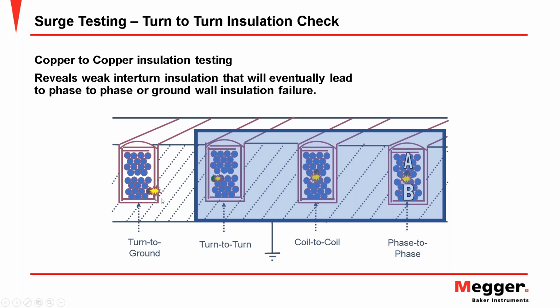So over here on this graphic, we see the ground wall insulation represented here in the slot between the conductor and the frame. The turn-to-turn or copper-to-copper insulation is between individual turns in the coil. It could possibly be between two adjacent coils, so copper-to-copper between coils. And if those coils happen to be in different phases, so if the top coil was, say, phase A, the bottom coil was phase B, that phase-to-phase barrier is also considered a copper-to-copper insulation barrier that we need to evaluate.